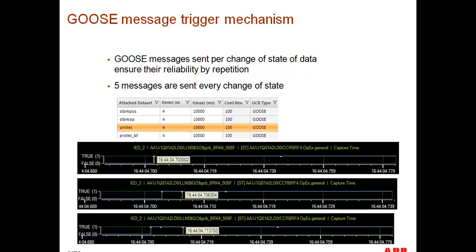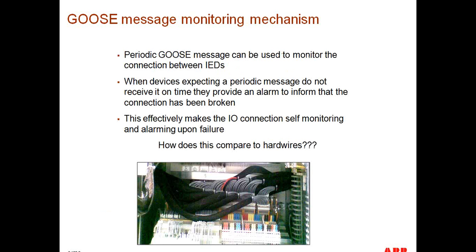Looking a little bit deeper into this, one of the questions that always comes up is, how come, if everybody sends information at the same time, it works? Well, Goose message reliability is based on repetition. Whenever a change of state occurs, we actually send 5 messages containing that same change of state. As you can see here, they are spaced out sequentially, and in the presentation this darker dot means that the change of state occurred. This is another time that we send the message, this is another time, and then this is another time. So we are building reliability by repetition.